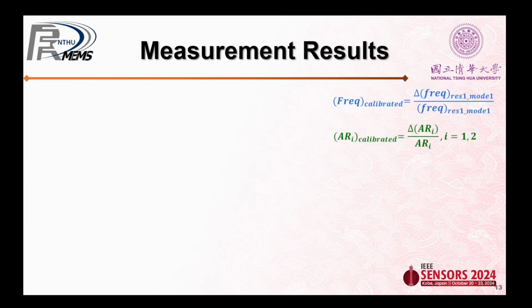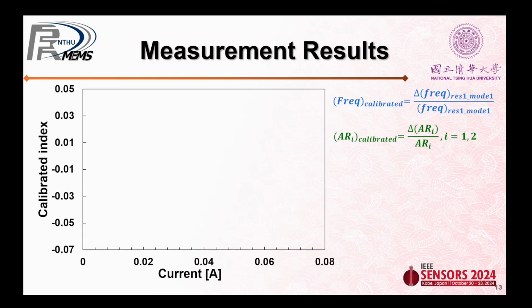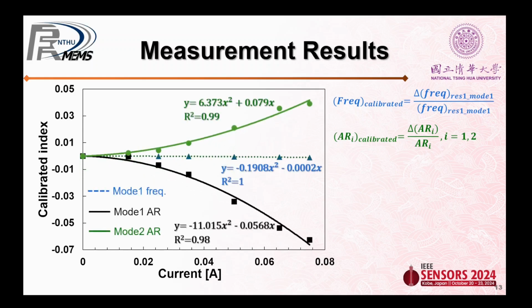We introduced a parameter from another group called the calibrated index. It's defined as the difference between the initial and final values, divided by the initial value, resulting in a unitless quantity. After recording and post-processing the data, we can plot this graph. The calibrated index has a squared relationship with the input current, as Joule heating is also related to the square of the stiffness variation. With an input current of 50 milliamps, the calibrated index of amplitude ratio is 65 times greater than that of frequency, indicating that using amplitude ratio as an output metric is more sensitive than frequency shift.